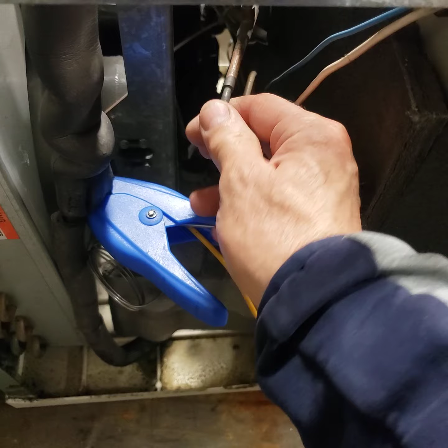When you hear that click, usually when the harvest starts, immediately this will open, the condenser fan will stop, the pump will stop, the water will be flushed. They all happen together. So if you put your hand here, between the metering device outlet and the evaporator inlet, and you don't feel this bypass pipe hot, I mean, it doesn't hurt you, but you should feel really warm. If it's not, and you see there's power here and this is clicking, there's something wrong with it. That's just so you know, in case you have some suspicion that the hot gas bypass solenoid valve is broken.